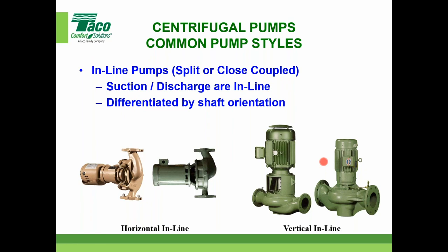You know, if you need a 500 GPM pump at 40 feet of head, and maybe the KV is the right one and is a point or two percentage higher. And maybe if it's 400 GPM at 40 feet of head, maybe the base mounted one's a little higher efficiency wise. But then the price wise, it's pretty close. So something to consider. People ask me that. So it's really your preference. Application wise, like a condenser water or chilled water, hot water, they're both going to hold up and do the job. So just make sure you understand that.